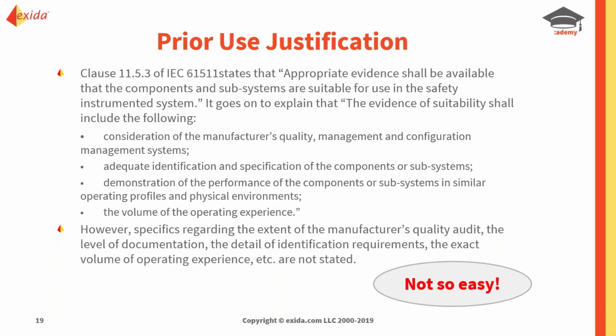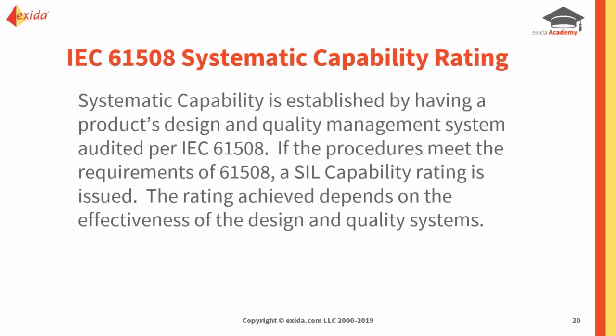Even if you check all the boxes, what level of rigor is enough? What level of detail is needed for documentation, identification of requirements, and how much volume of operating hours? Nothing is clearly stated in the standard. For proven-in-use or prior use, or even Route 2H, if you're looking for SIL compliance, we're talking at least 10 million operating hours. Here at Exida, we like to use 30 million as a conservative approach.